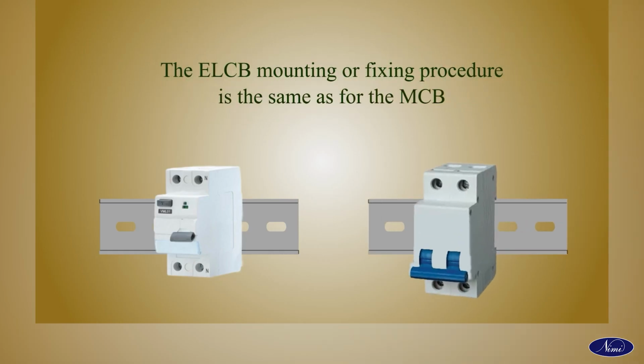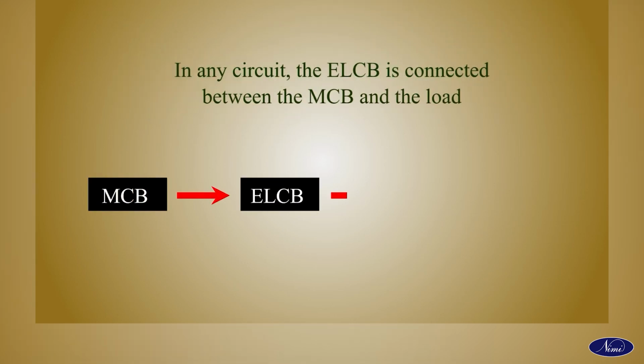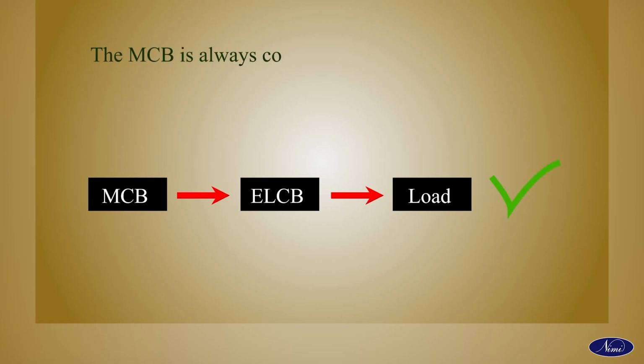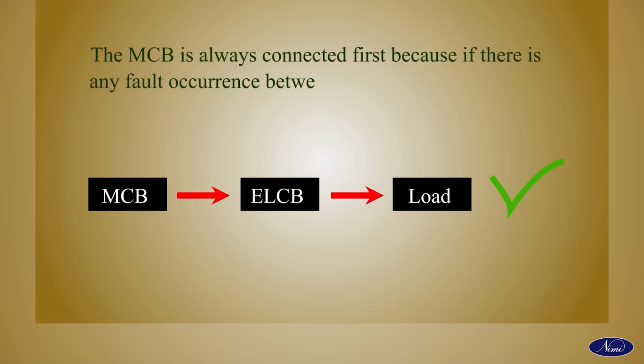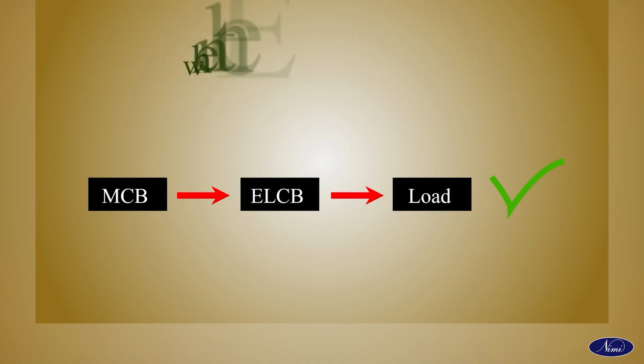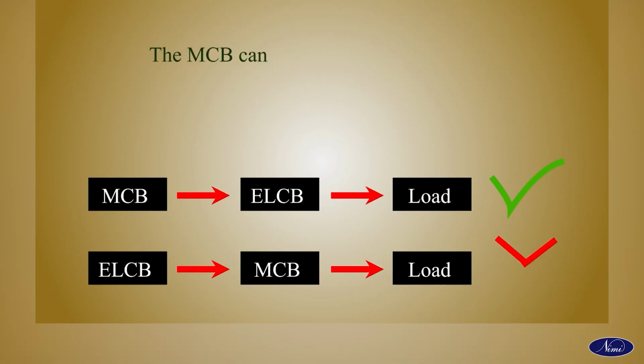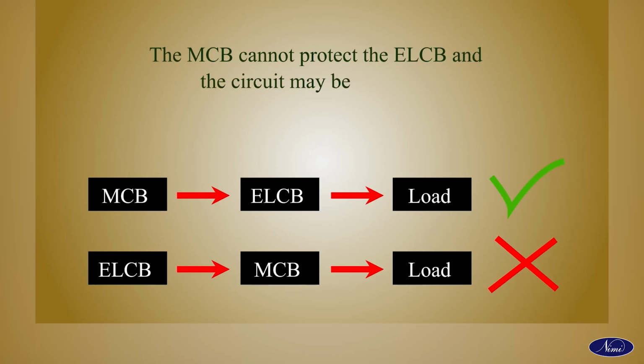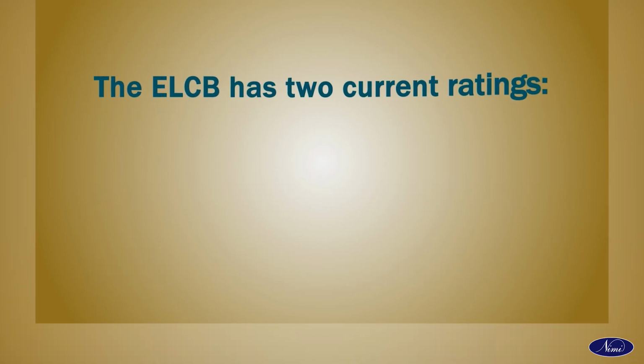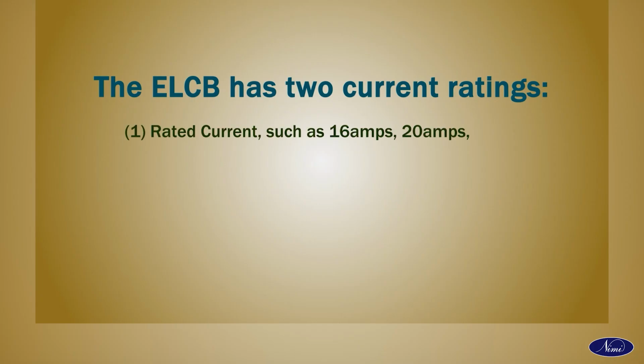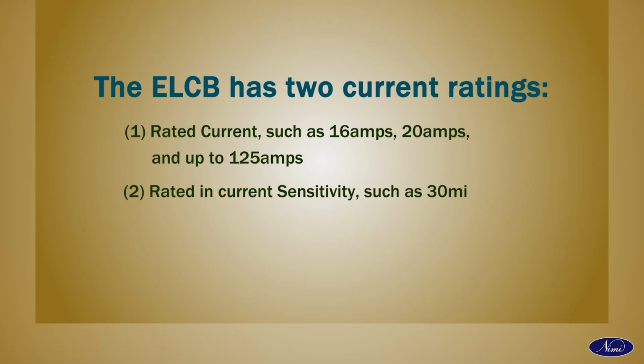The ELCB mounting or fixing procedure is the same as for the MCB. In any circuit, the ELCB is connected between the MCB and the load. The MCB is always connected first because if there is any fault between the ELCB and the MCB when the ELCB is connected first, the MCB cannot protect the ELCB and the circuit may be damaged. The ELCB has two current ratings. One, rated current such as 16 amperes, 20 amperes and up to 125 amperes, and two, rated current sensitivity such as 30 milliampere, 100 milliampere and 300 milliampere.